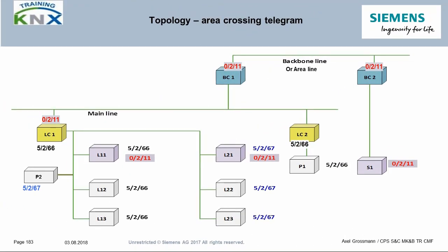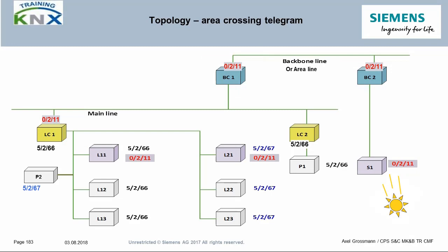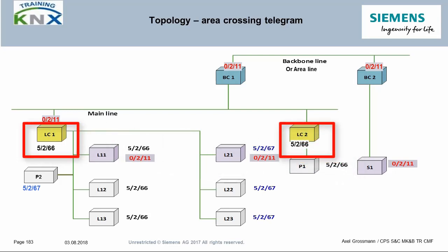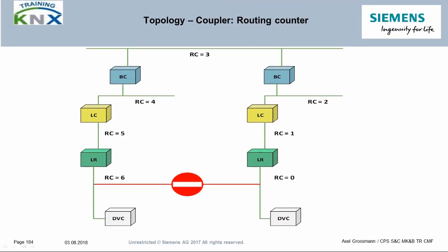If it is a larger building in which several areas exist, the light sensor can now be installed further away. The group address 0211 must now be entered in three couplers: the two area couplers 1.0.0 and 2.0.0, as well as the line coupler 1.1.0. In this picture, the P1 key has also been swapped out, meaning that the group address 5266 must also be entered in the filter tables of couplers located on the connection route from P1 to L11, L12, L13 — namely 1.1.0 and 1.2.0.